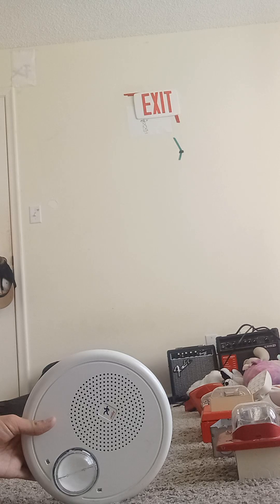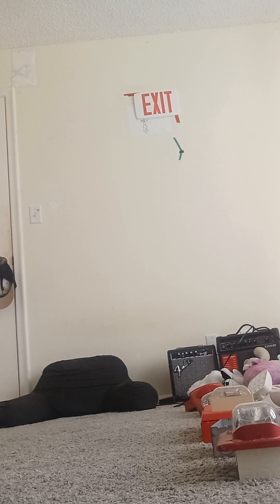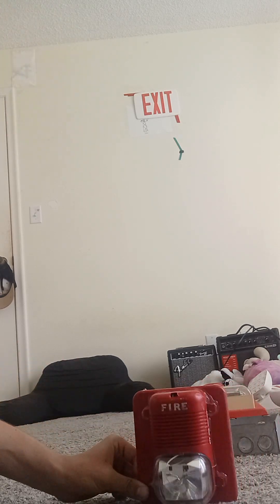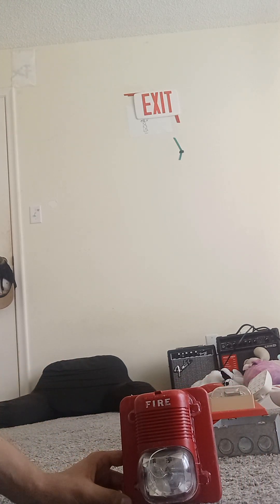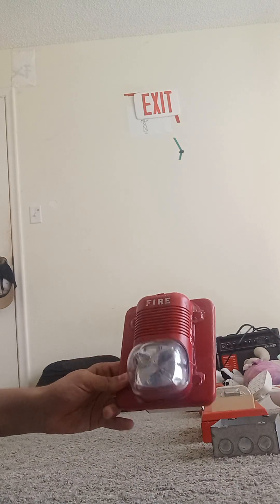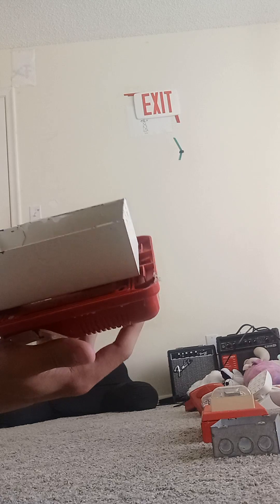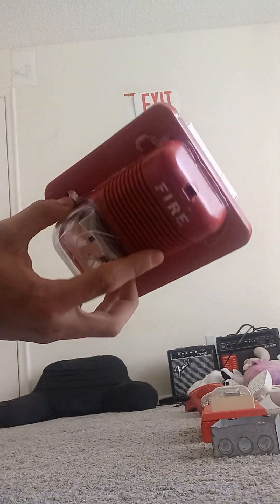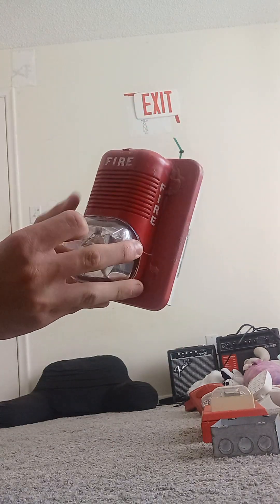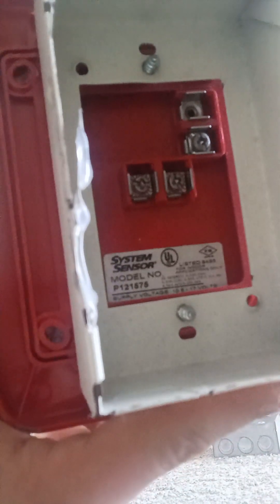Let's move on to our second row, then the third row, and then we'll move on to the exit signs. Right here we have our System Sensor P1215-75. This is a SpectrAlert Classic horn strobe. As you can see I have super glue around it even though it's hanging off. This thing is messed up. Right here it has its own back box. Model number P1215-75. There's one screw missing here, and we have positive and negative wires.